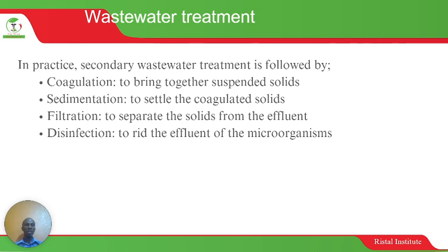So by bringing them together in coagulation, the sedimentation will do the work of settling them down on the floor of that sedimentation tank. Then after that, this water will go into the filtration tank, which will separate those solids from the water. After this water has been separated from these solids, then you will now disinfect it. Okay, so disinfection, which is almost always the last process of treating any wastewater or any water per se, is to get rid of those microorganisms.